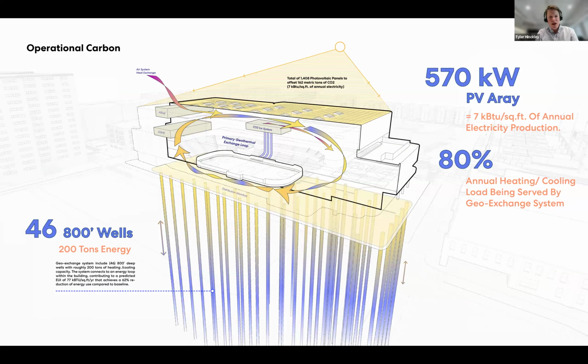And what that allows us to do, similar again to the RU project, is a hybrid system where we have ground source heat pumps, air source heat pumps, the waste heat from the ice system, all feeding into an energy loop throughout the building. That system, the geo-exchange system, can cover 80% of the annual heating and cooling load. The rest would be covered by the air source heat pumps.